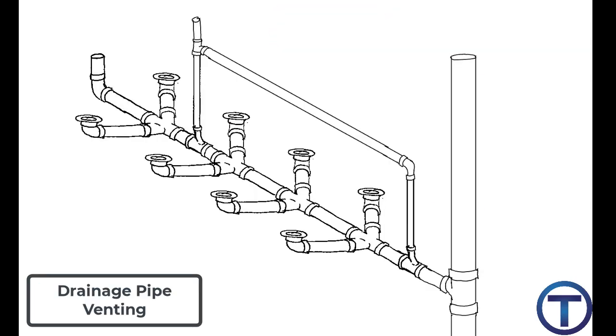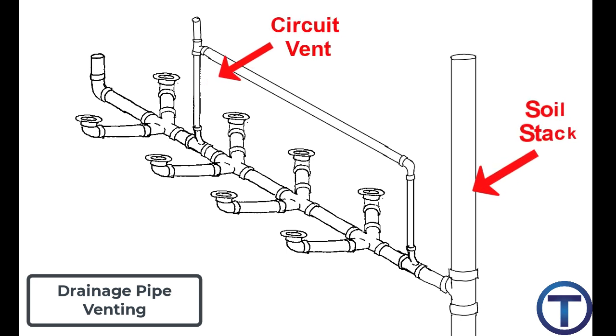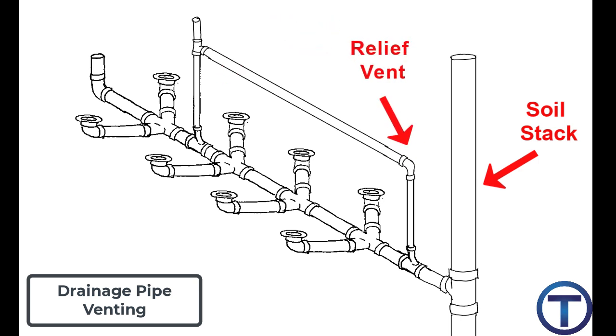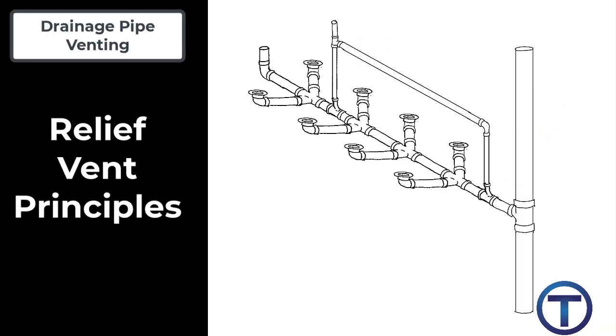There is another condition you need to be aware of if you're using circuit vents. Any circuit vent that connects to a stack which is receiving waste from a branch interval above that floor level must be provided with a relief vent. This applies to both International and Uniform Plumbing Codes. Here are a few principles that will help you understand the relief vent.